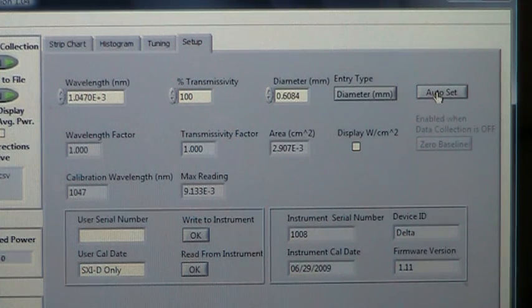There's also a very handy auto set button. It's like the auto set on an oscilloscope. When you're just setting things up initially, you can get your laser running, line the detector up, and then hit auto set. It will automatically look for the appropriate range and trigger level to start this instrument working.